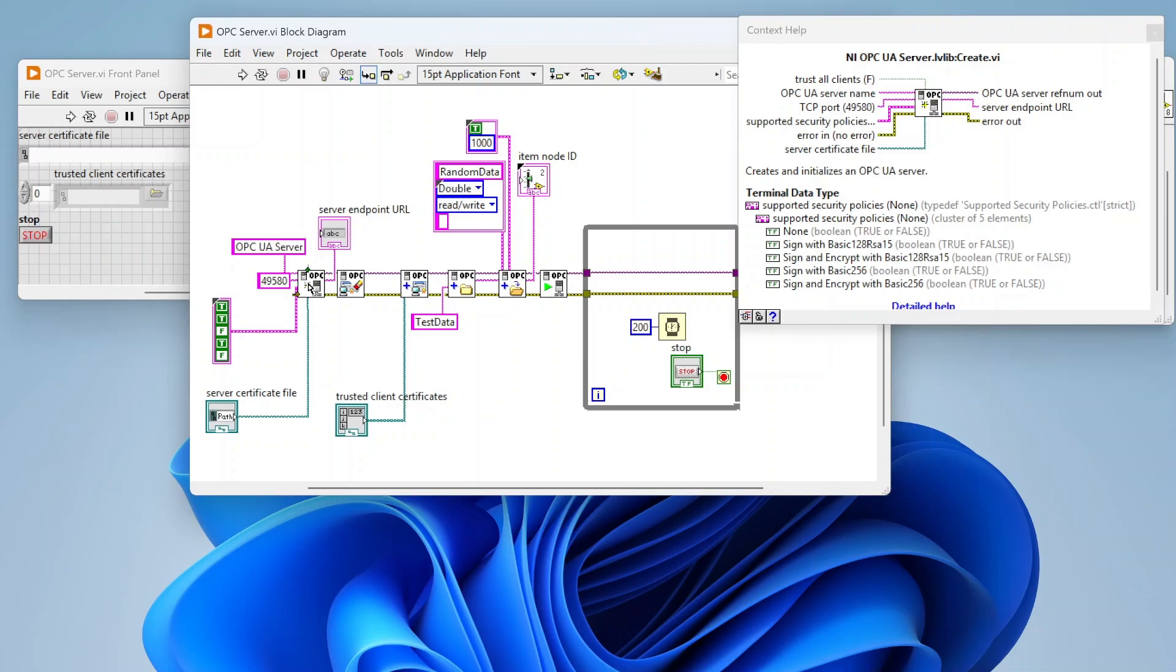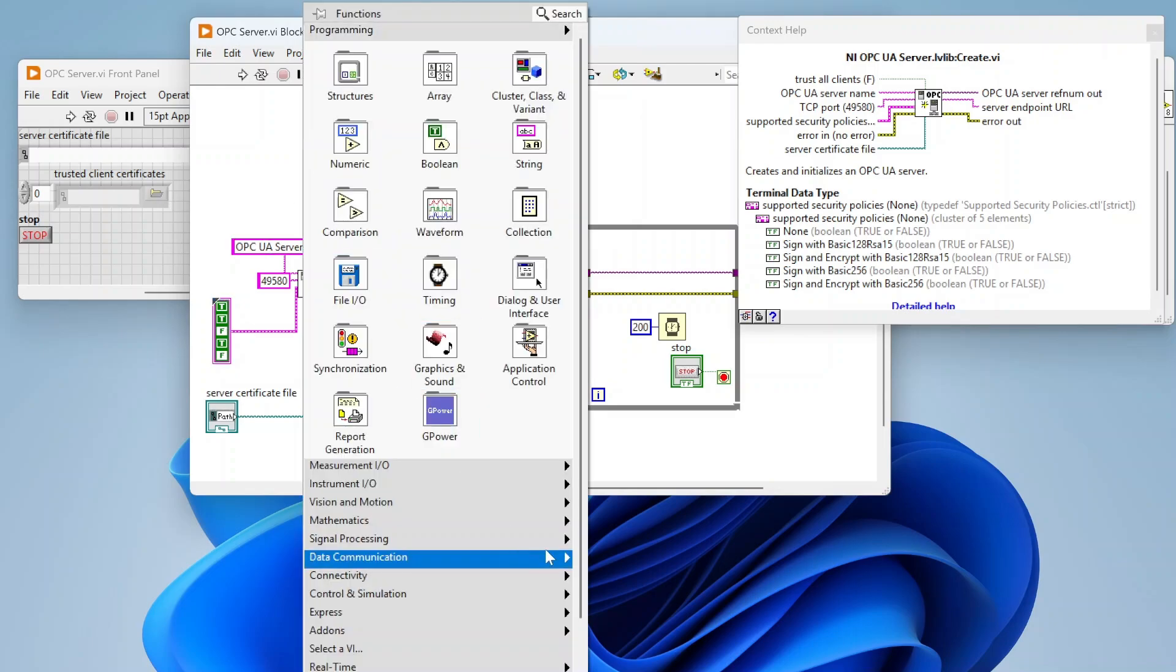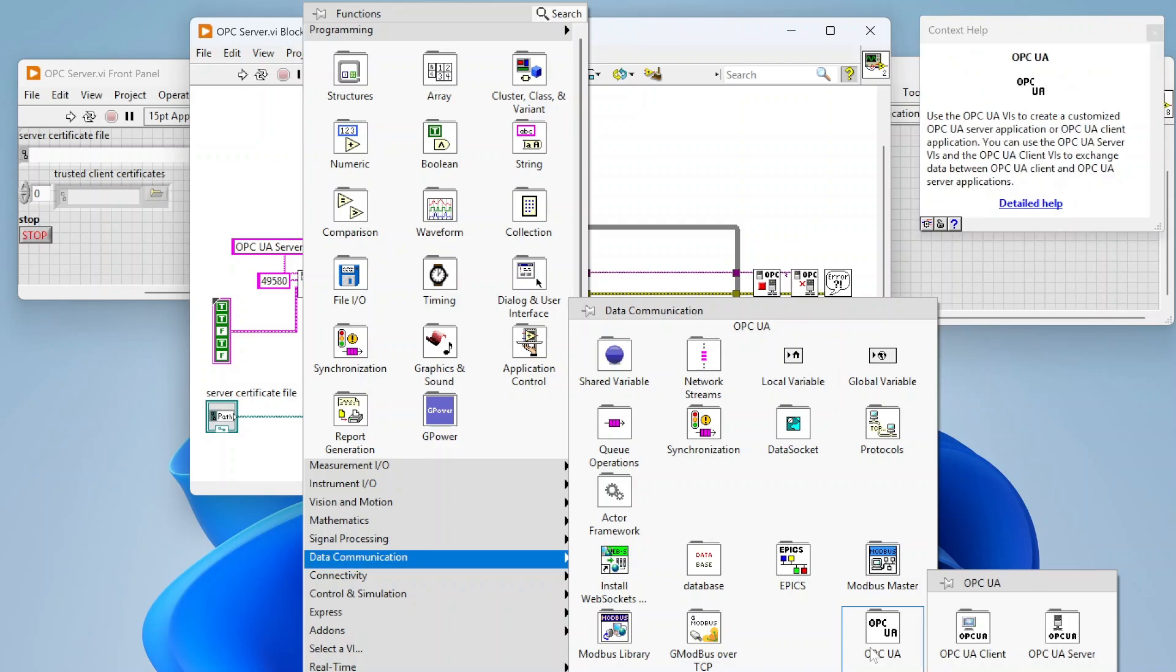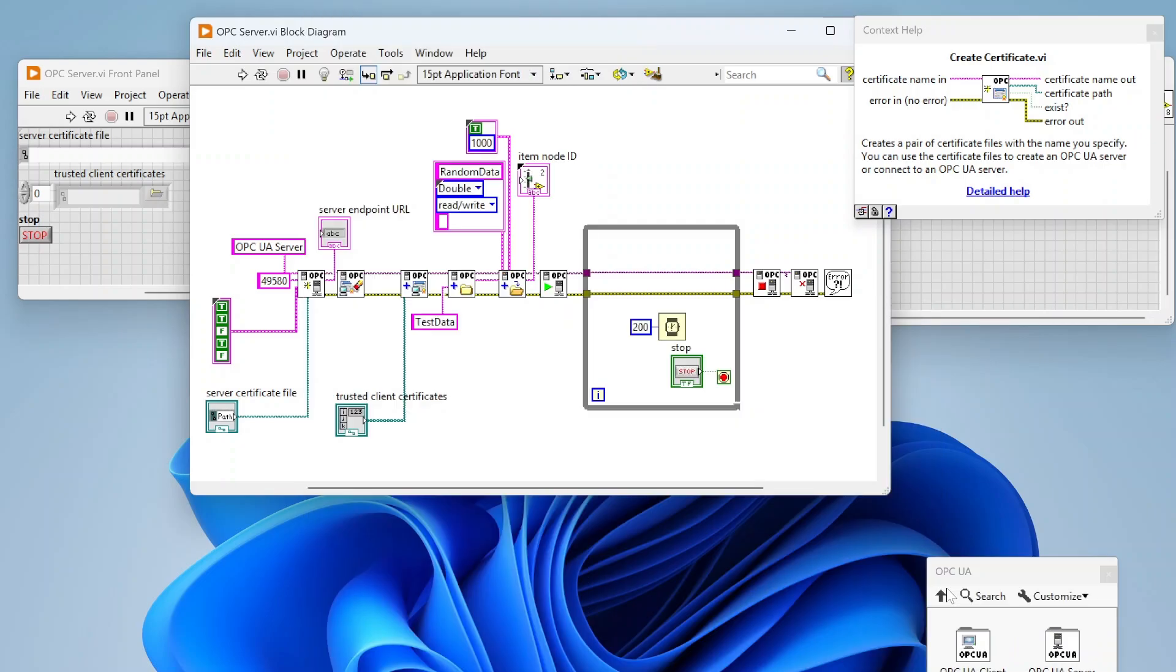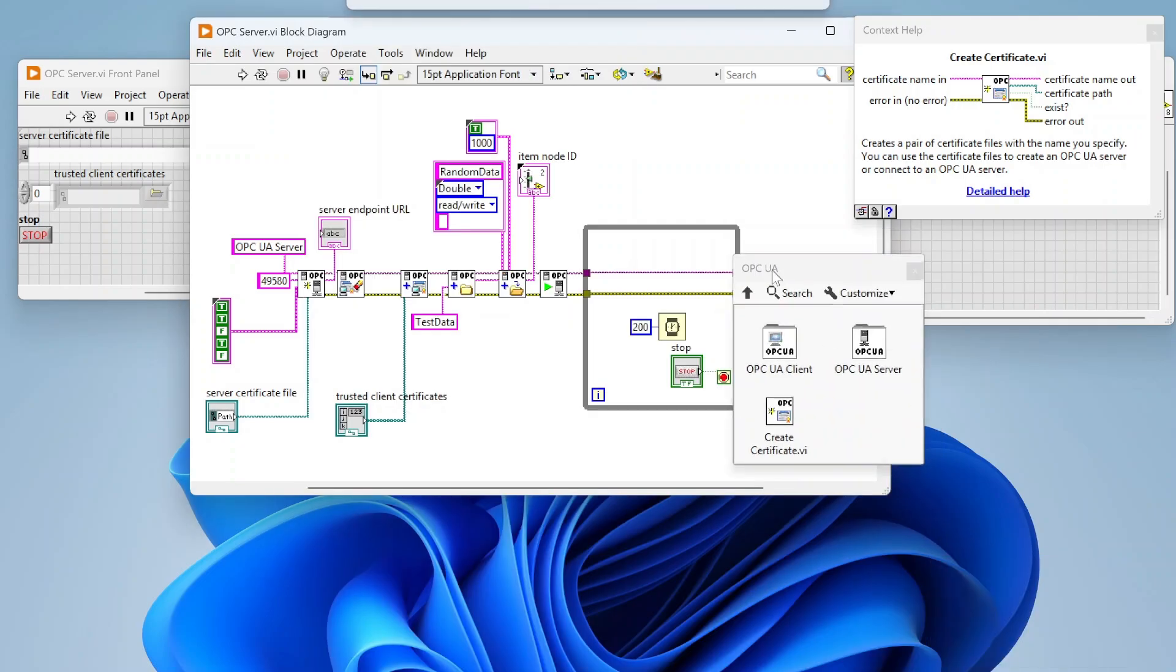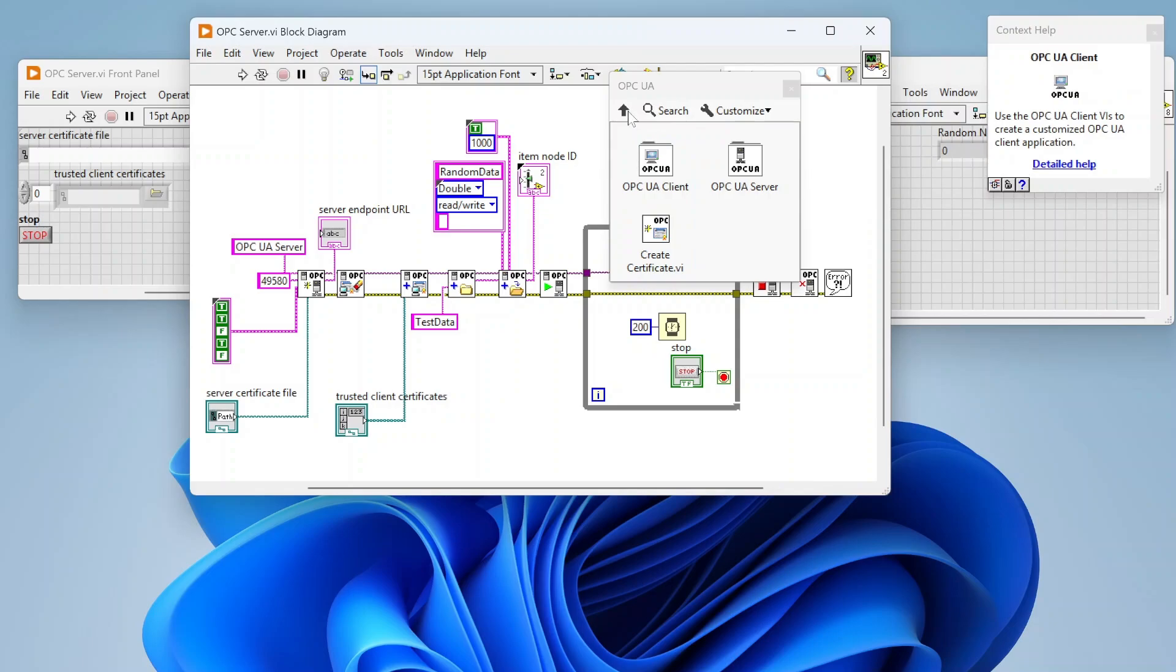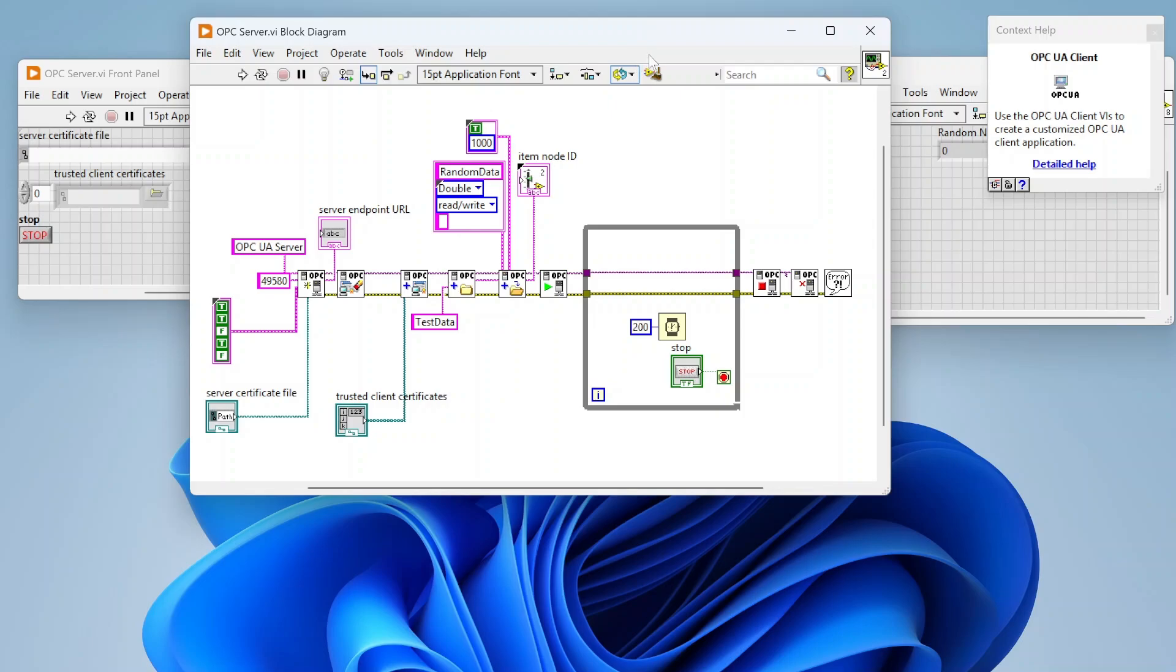You're able to pass in a server certificate file if you're using encryption and signing. If you go into the OPC UA, there is this create certificate function that allows you to pick a name for a certificate and it generates the certificate files for you, so you don't necessarily have to get those from a certificate authority through your IT team.